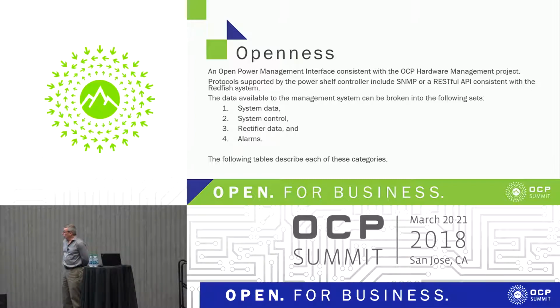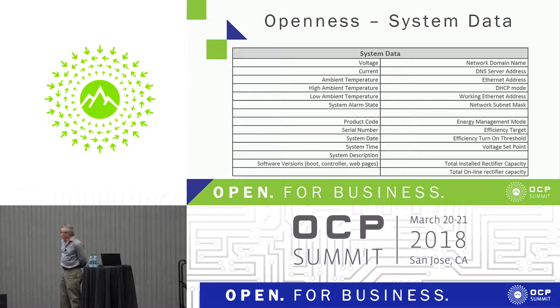We're also looking at probably a contribution on a battery module that we've developed for another application. Individual rectifier data, any alarms generated by the system, over voltage, under voltage, excess current, all those sort of general alarms. Rectifier failure, we have numerous ways of detecting rectifier failures. In terms of the system data available through the interface, the usual voltage, current, temperature, part numbers, all that sort of thing.